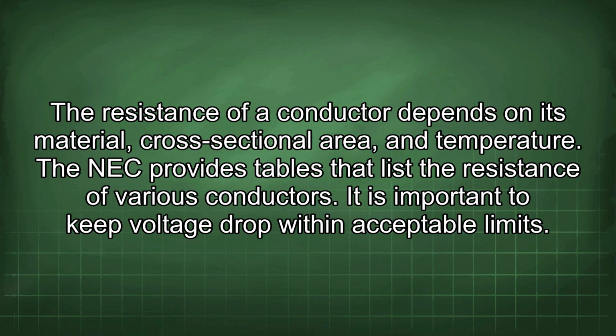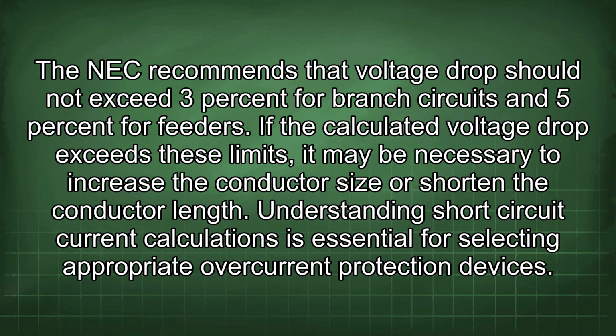The resistance of a conductor depends on its material, cross-sectional area, and temperature. The NEC provides tables that list the resistance of various conductors. It is important to keep voltage drop within acceptable limits. The NEC recommends that voltage drop should not exceed 3% for branch circuits and 5% for feeders.